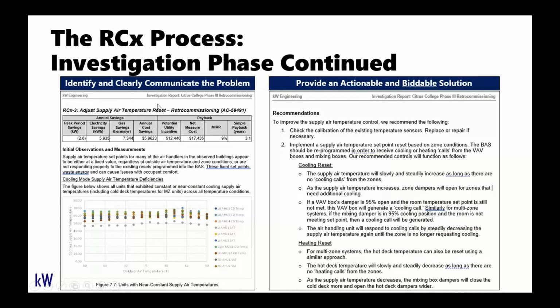Now, in addition to identifying the problem, we also want to identify our proposed solution. And I think this is really where you'll see a big variety in the quality of audit reports or retro commissioning reports. Some might say our recommended solution is to implement a supply air temperature reset and vary the supply air temperature, and leave it at that. That's all well and good, but it's not actionable and it's not biddable, because the devil's in the details of what is actually going to be required to implement a project.